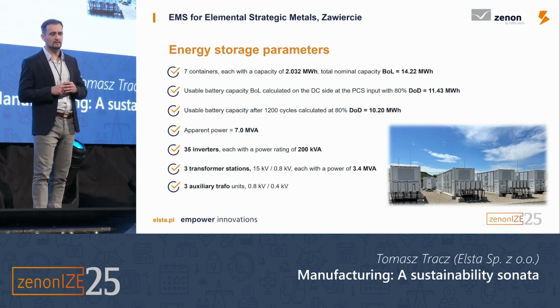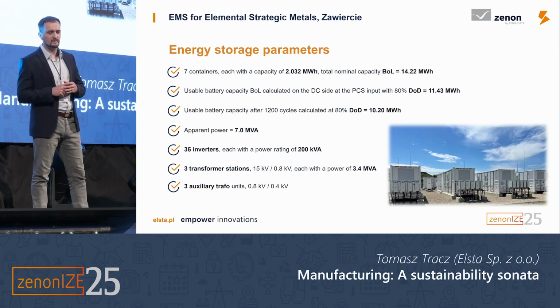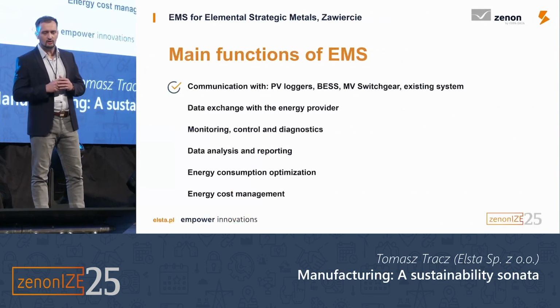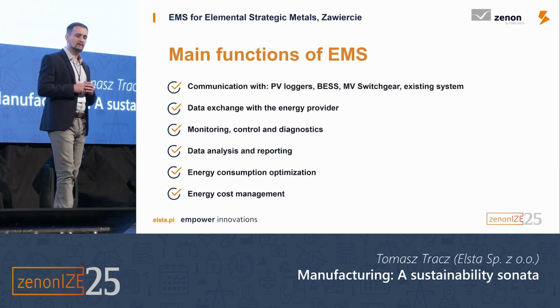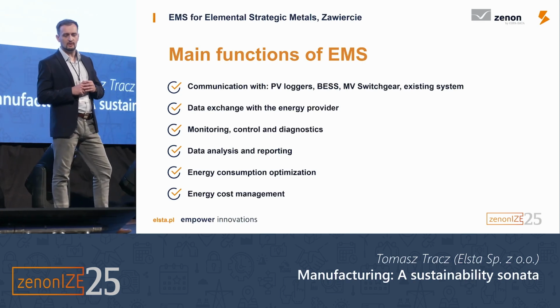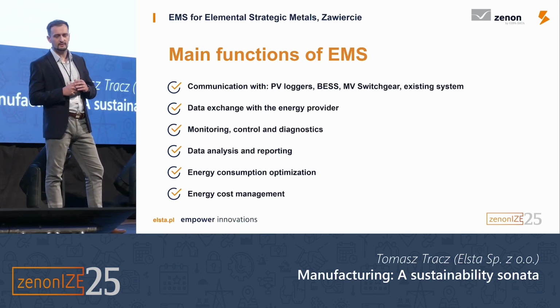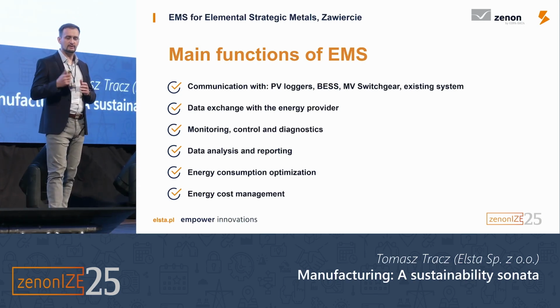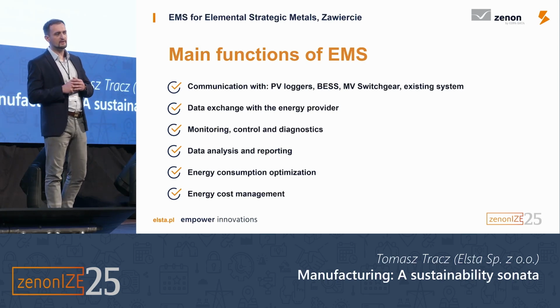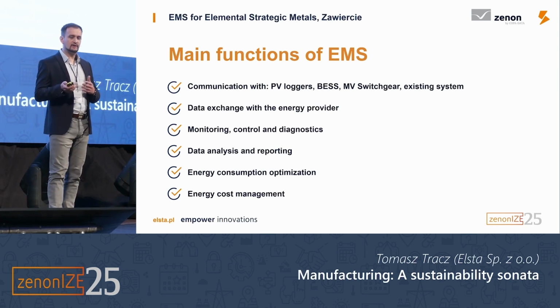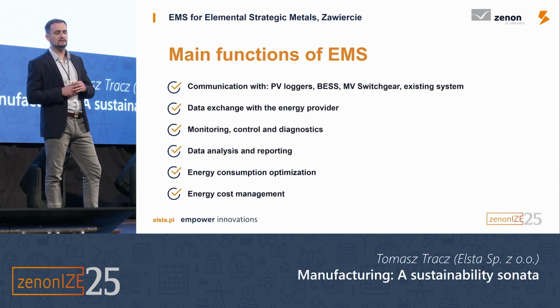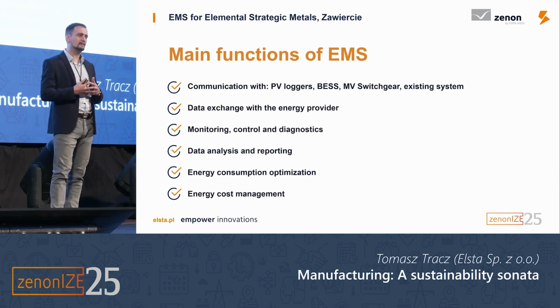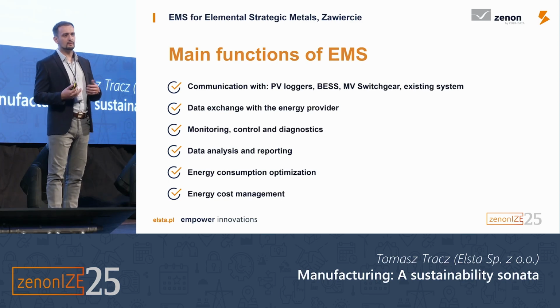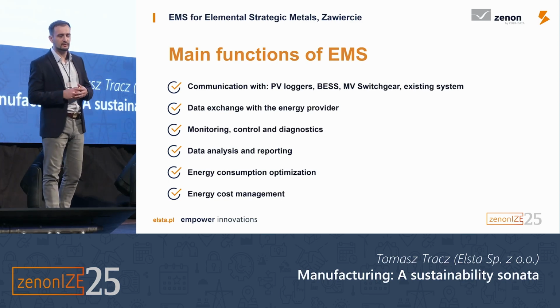And we also had to make sure that all loggers incorporated in this are working properly. So main functions of this EMS, as you know, there's communication with PV loggers, battery energy system, MV switchgear, and also the existing system, because there was an existing SCADA, which we needed to incorporate a lot of data into, in order to be proactive, to plan, to predict the conditions.